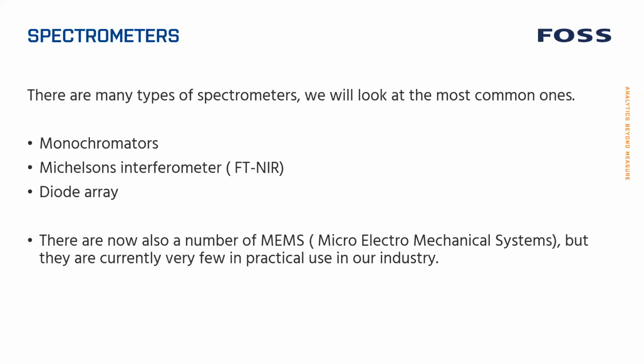Okay, let me see if I can go back here. So spectrometers, I will go through the three most common ones. It's the monochromators that we are using, the interferometer, also called FT-NIR, and diode array. There is also a number of what's called MEMS, micro electromechanical systems, but they're not really practical. And I would say very few of them are in use in our industry, one of the reasons being they are so small. So they have a very small light beam. And when you use samples like grains and pellets and things like that, you want big light beams and big detectors. A tiny beam will only work if you have something that's totally homogeneous. So they're not practical.